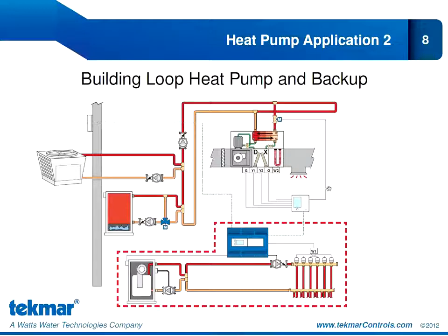Since each unit is controlled independently, some of the units can be in heating mode while some can be in cooling mode, and each unit will absorb or release heat to the loop. Traditionally, this type of system was controlled with customized building automation systems, but we can accomplish the same thing by installing a 557 in each of the units, and we can connect all the 557s to a tekmar Gateway 483 control so that we can have remote access over the internet. We can have a similar control solution at a significant reduction in cost with the 557.